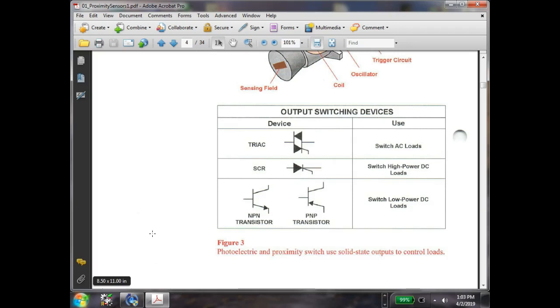Triacs are used in an AC circuit. Every one of the devices we're using this semester uses a triac as the output. Unfortunately, triacs will never drop 0 volts—they'll get close, but never drop 0. So in our diagram we draw a contact, but these guys don't have contacts. The only one we looked at with a physical contact is the magnetic reed switch. All the other sensors we'll use this semester use triacs as their output, because our sensors are all AC sensors.